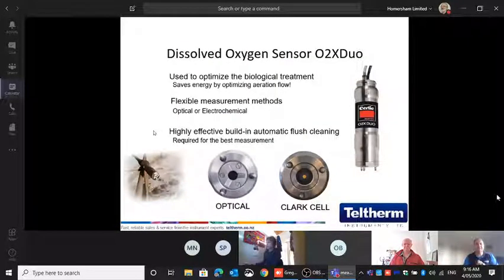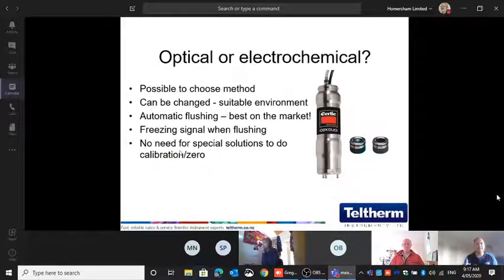With the DO sensor, we have optical or galvanic cell. We are not more accurate or better than anyone else. This is exactly the same technology. We use the same sensors. Where we know we are better is the cleaning. From those three points, we spray up to 2 bar water or air directly onto the lenses, so cleaning is very effective. The advantage, like you saw this morning, is you can unscrew the cap here, pop out the sensor and plug in another sensor. It doesn't matter if you've got optical or galvanic. Very easy to do. At the moment we standardly supply a galvanic cell, but if people want an optical, absolutely not a problem.